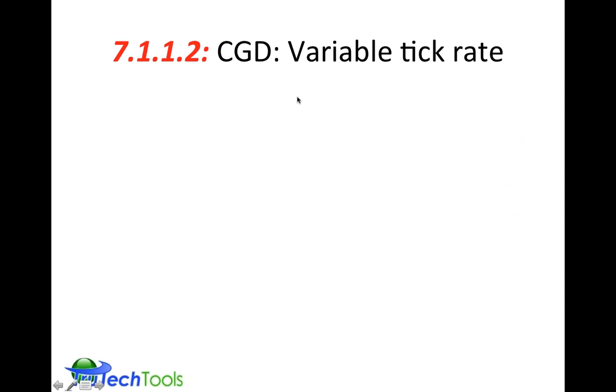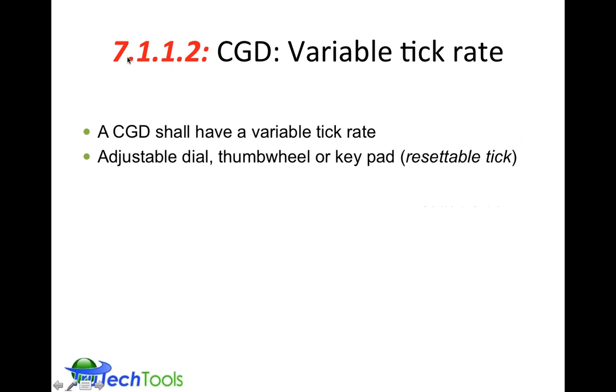The combustible gas detector, and these numbers here are directly from the BPI 1200 standard, so you can look them up and reference them, requires a variable tick rate. So a combustible gas detector shall have a variable tick rate. It could be with an adjustable dial, thumb wheel, or a keypad, a digital adjustment, or something like a resettable tick rate.